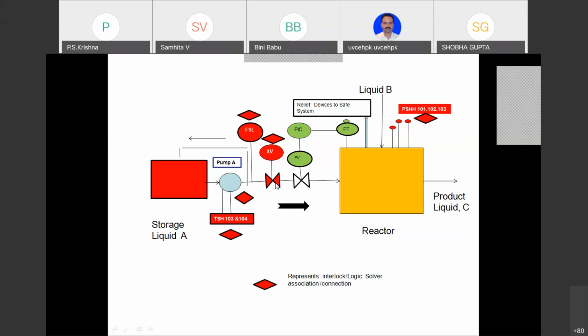And then we go, and still the hazard analysis is not over. Then they say, hey, what about this? We have not come to the pump yet. So for the pump, they said, what is the most dangerous thing? We said high pressure, low pressure, this pump not running, electrical voltage failure, all that we have done. So then someone said, hey, we have got a problem. You remember the churning of that liquid takes place when this pump is running and not able to deliver for some reason, so it gets heated. And I said, that 6 into 10 to the power of minus occurrences per year means this pump has exploded because of the heat and the liquid inside it. Then they said, okay, we have to put something. Then we did some calculation and all that, and we finally arrived at putting 2 sensors. Why 2 sensors? Redundancy.